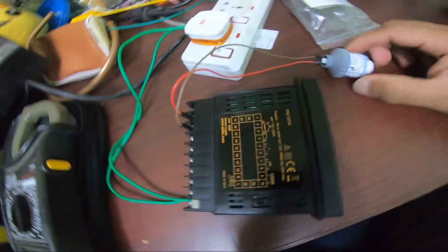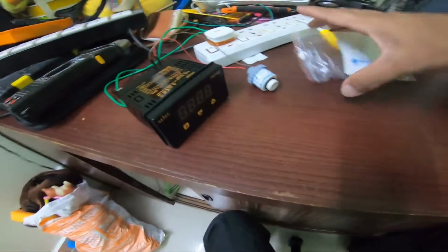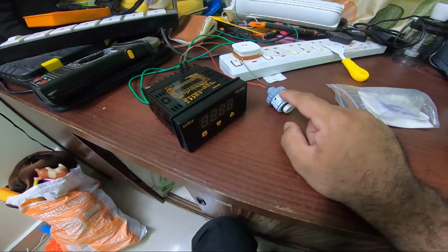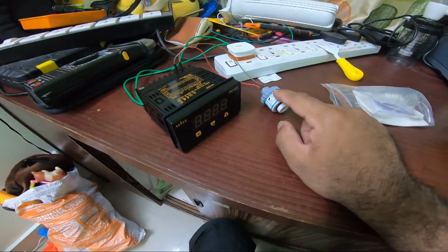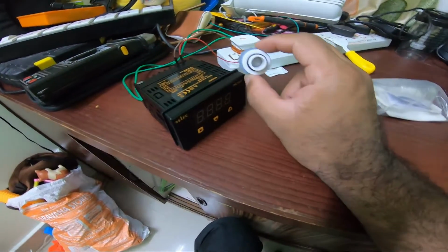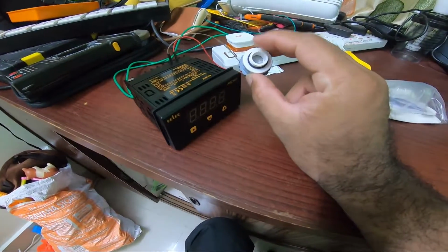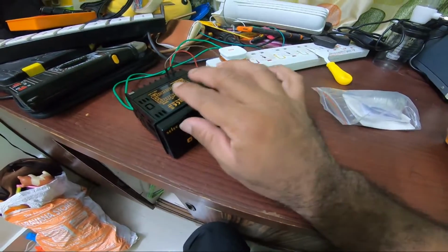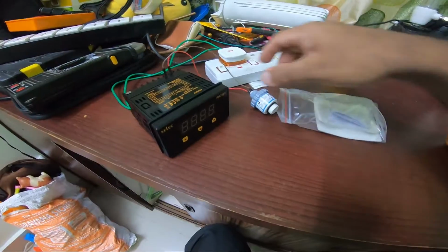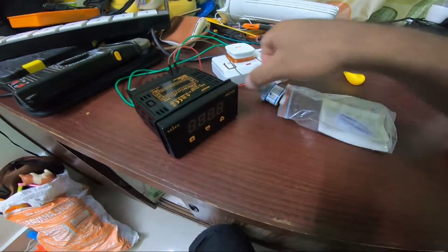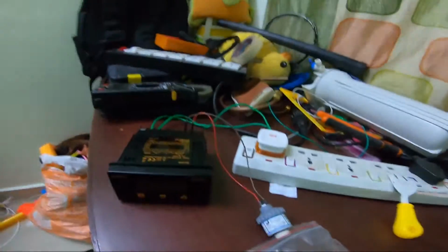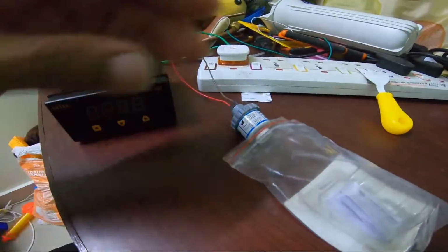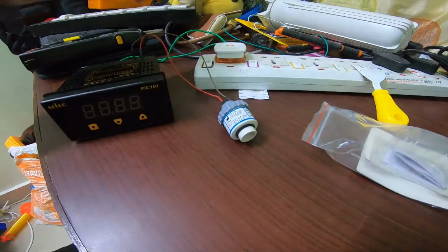Okay, great. Why did I keep this inside a cover? Because this has a life of 1 to 2 years maximum, because once you open it, the chemical inside gets oxidized and it has an expiry date. So when I keep it inside, I will be able to accurately measure the 21% of oxygen. That's the reason I kept it.